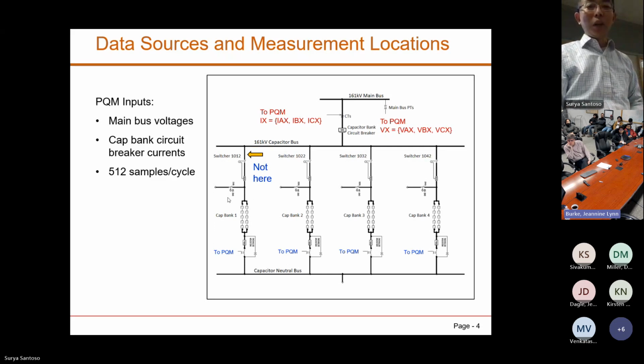We have a capacitor bank right here - this is bank 1, bank 2, bank 3, and bank 4, all identical. Now we have a circuit switcher, whose purpose is to energize a capacitor bank in and out. This circuit switcher has a pre-insertion inductor to reduce the inrush current. Then we have a circuit breaker, whose purpose is to interrupt fault currents.